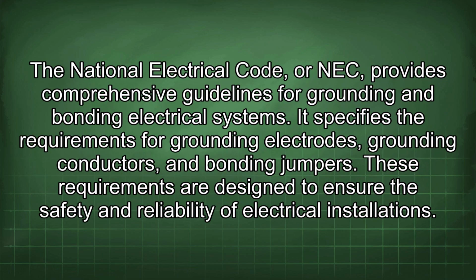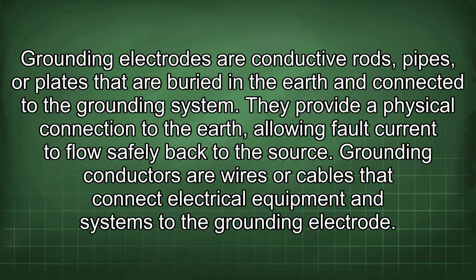The National Electrical Code, or NEC, provides comprehensive guidelines for grounding and bonding electrical systems. It specifies the requirements for grounding electrodes, grounding conductors, and bonding jumpers. These requirements are designed to ensure the safety and reliability of electrical installations. Grounding electrodes are conductive rods, pipes, or plates that are buried in the earth and connected to the grounding system. They provide a physical connection to the earth, allowing fault current to flow safely back to the source.